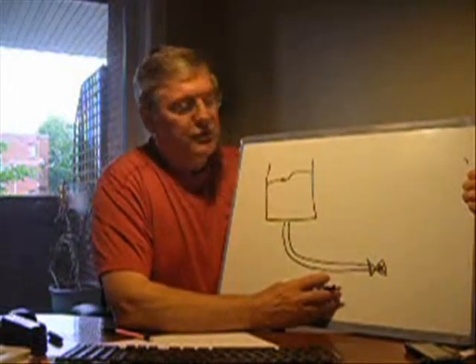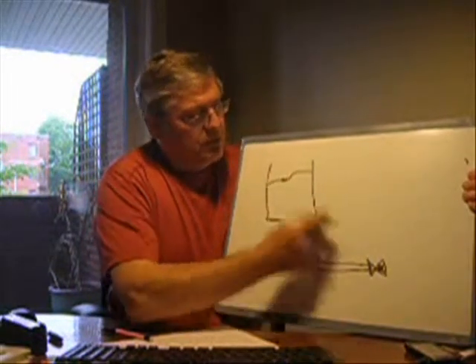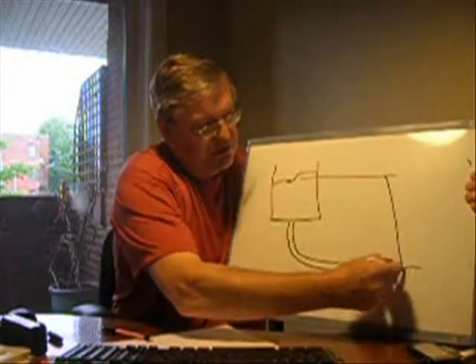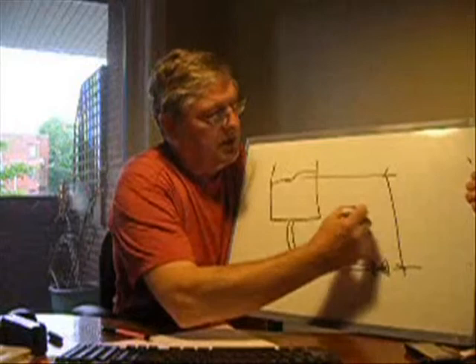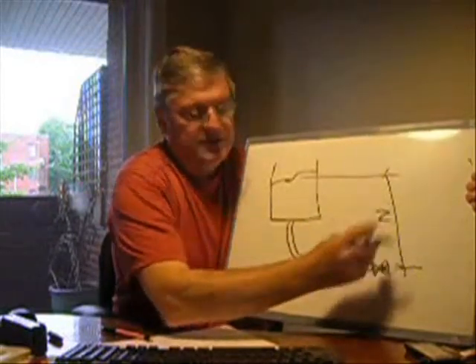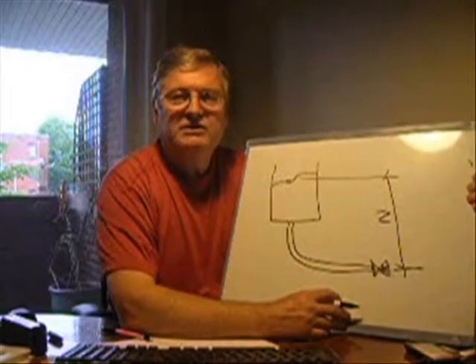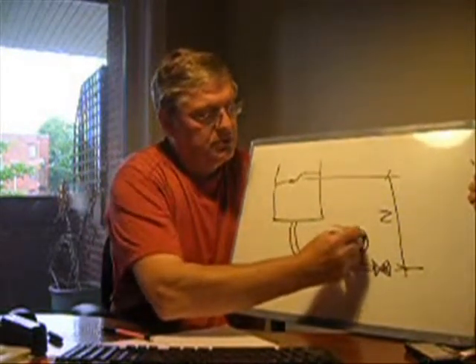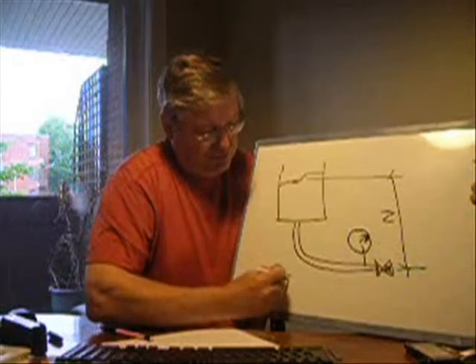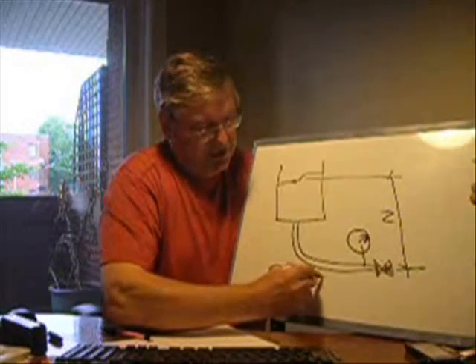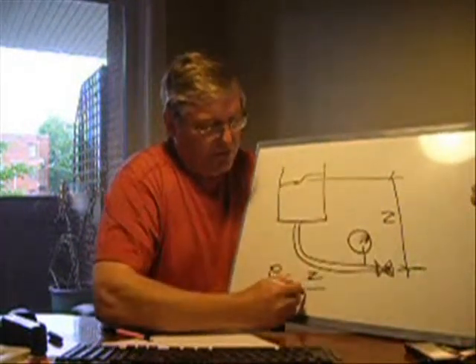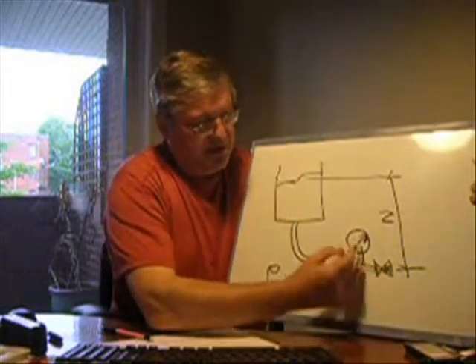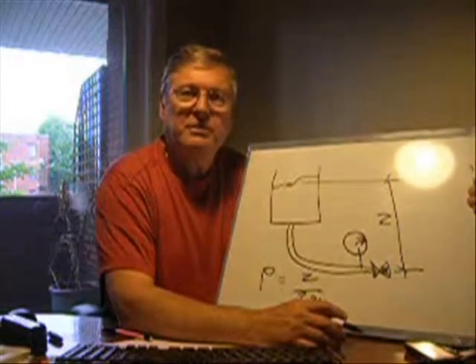That definition works well for us too. We would call this static head — taking the two heights and subtracting them, labeling that Z. If I wanted to know the pressure at a point, I could put a gauge there, and the pressure would equal Z, the height measured, divided by 2.31. Or if I had the pressure but not the height, I could calculate the height, since height can sometimes be difficult to measure directly.